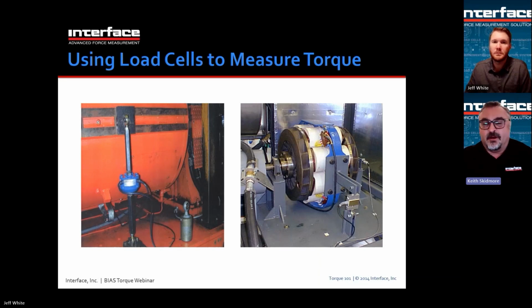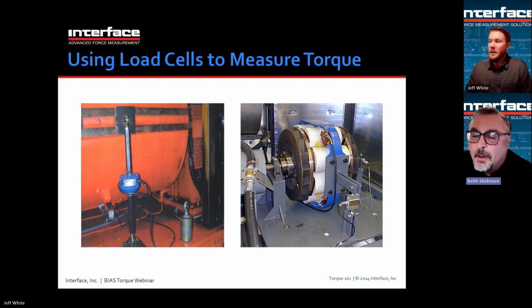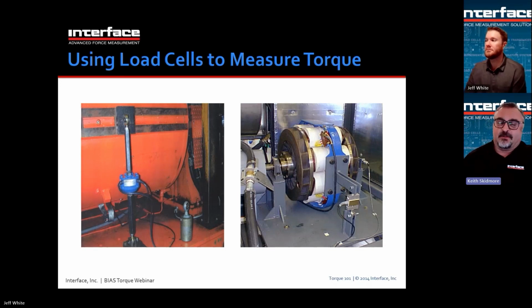Distance of the lever arm times the force measured is torque. And on the right side, a little bit different looking system, but quite similar, where there's a lever arm and an S-type load cell providing the reaction. So instead of a reaction torque sensor, you can actually react torque using load cells. And that's what this is an example of. Sometimes this could be easier, less expensive, less complicated, depending on the system.